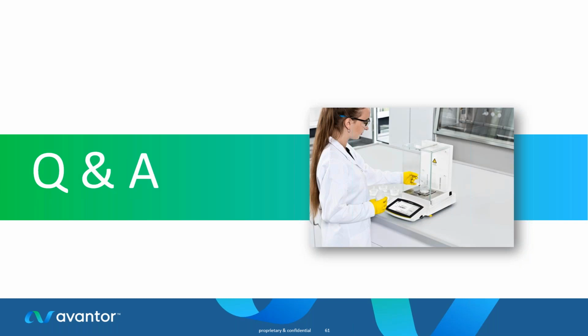We mitigate this by, in the balance, we have various filters. For example, we have one which is called weighing in a fume cabinet. So if you enable this setting, the balance will integrate the weighing signal, and it will do its best to minimize the effect of any vibrations or any air current effects within the fume cabinet itself. So there are various settings on the balance which we can use to try and mitigate any of these external influences.